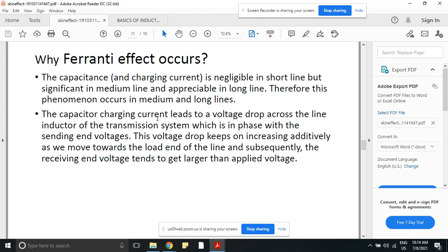The capacitor charging current leads to a voltage drop across the line inductor of the transmission system, which is in phase with the sending end voltage. This voltage drop keeps on increasing additively as we move towards the load end of the line, and subsequently the receiving end voltage tends to get larger than the applied voltage. So that is the reason for the occurrence of the Ferranti effect.